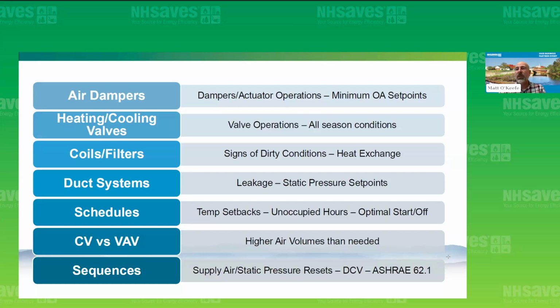And then just getting eyes on things like filters and coils can tell you a lot about maintenance needs. Sometimes a unit faces more open areas and can fill up with leaves and pollen, et cetera, and needs more frequent cleaning and service, or they're only changing out filters and never getting eyes on coils. Those coils can get dirty, and then your energy transfer just isn't there. Air ducts and static pressure sensors can tell you a lot if there are spots where downstream pressures can't be maintained, indicating leaks, or the opposite, opportunities to run at lower set points, saving fan energy.